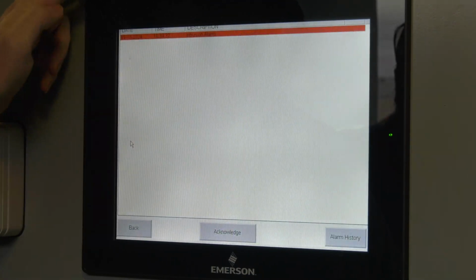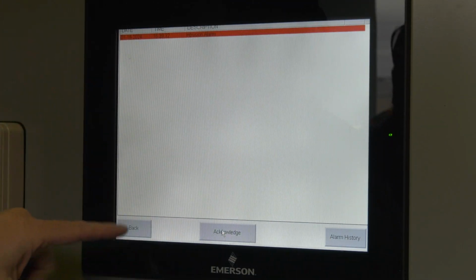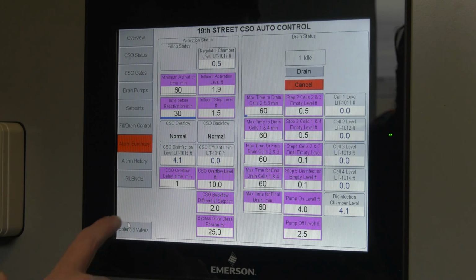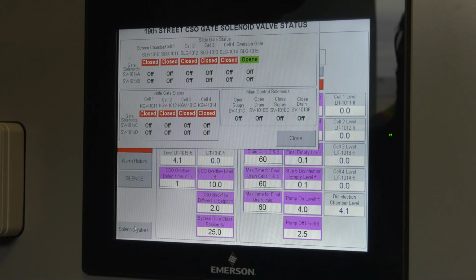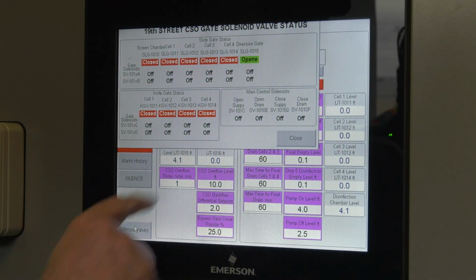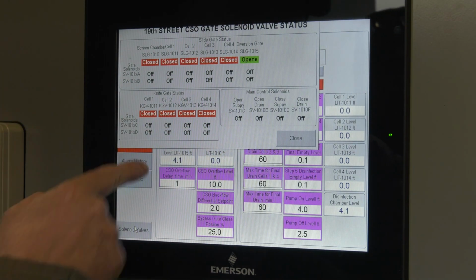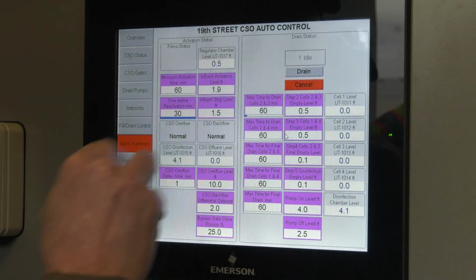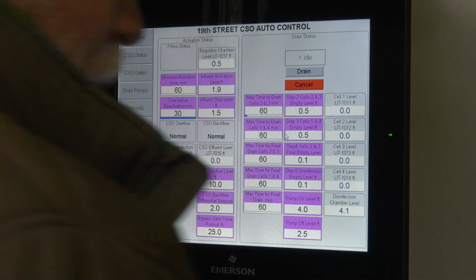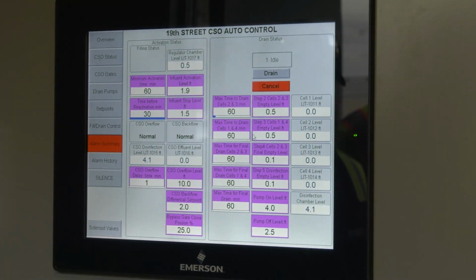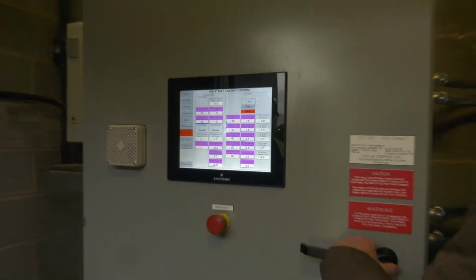That's it. Should be it on this one. Intrusion alarm. That's because we got the door open. All right, and we got the solenoid screen, which shows you which solenoids are energized. Makes it easier to troubleshoot and know what's going on. Let's see here. We've got an emergency call button on the front.